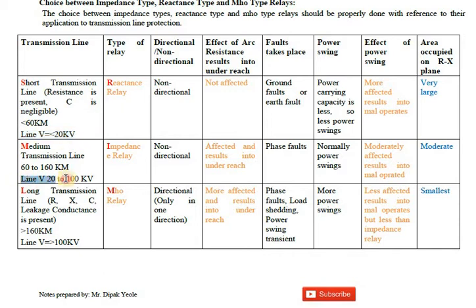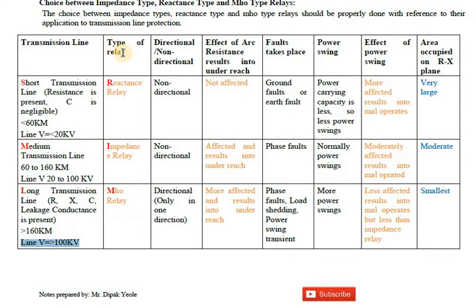Similarly, by voltage: less than 20 kilovolts is a short transmission line, 20 to 100 kilovolts is a medium transmission line, and greater than 100 kilovolts is a long transmission line. The corresponding distance relays are: reactance relay for short, impedance relay for medium, and Mho relay for long transmission lines.